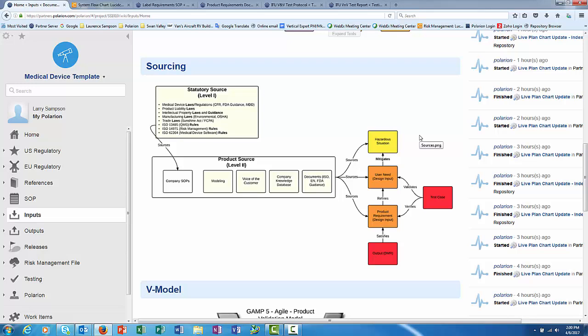With 14971 for risk management as an example, the company will pre-process those requirements into a company SOP, and then the company SOP is how we operate under that standard. So the company SOP impacts the product directly, but a lot of these other standards don't.